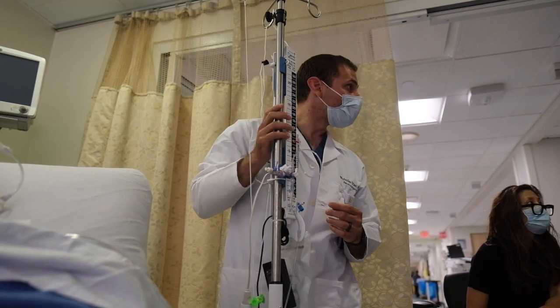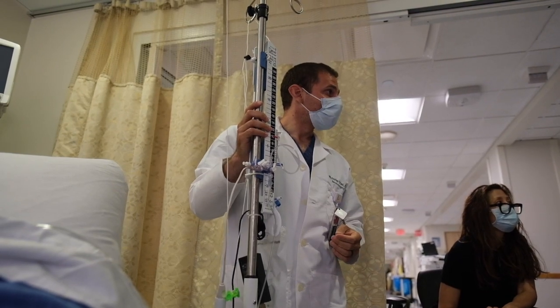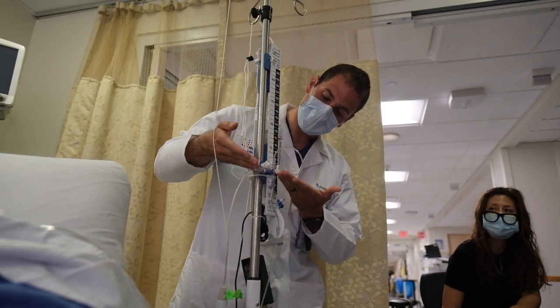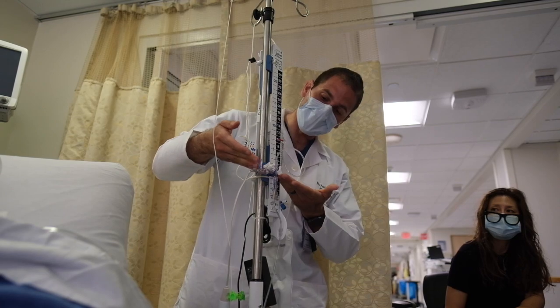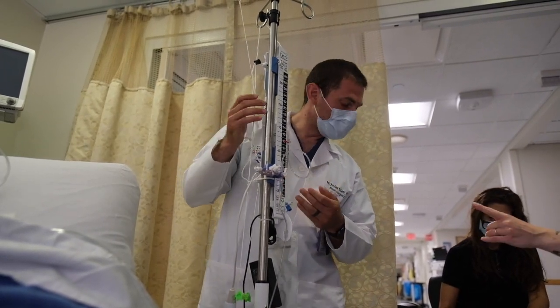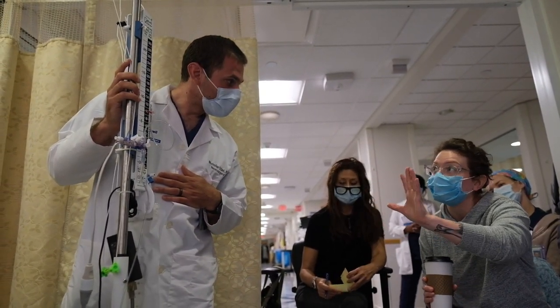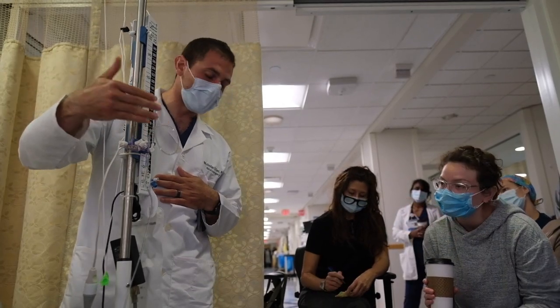So Nick, sorry, just quick. So the transducer, that's where we're leveling. Correct. This is where it should be leveled with the tragus. And the transducer, it's just full of air. You're not priming it. You don't prime it. You just pop it on, and that's it.